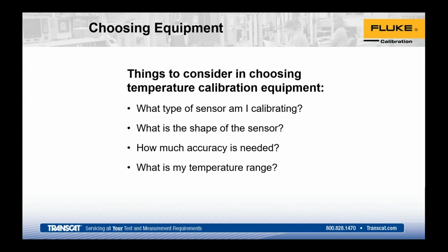So with that accuracy need, in the industry it's been 4 to 1 as long as I've been around. Not related to temperature, but in some of the other disciplines, the technology is progressing. So we're seeing, potentially in electrical and pressure, sometimes you can't maintain a 4 to 1 because the actual standards don't have that capability. So sometimes it's brought down to a 3 to 1 or 2 to 1, just because technology is progressing well on that side of the fence. But for temperature, usually it's 4 to 1, or you have to disclose an overall uncertainty of the calibration.